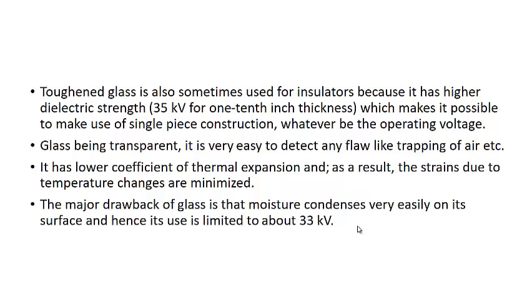Now, there is one major drawback, that is the moisture condenses very easily on its surface, which makes its dielectric strength reduce drastically. So, because of this drawback, its use is limited up to 33 kV.